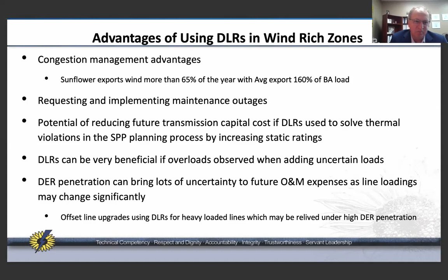So advantages of using DLR, I put them down here. Congestion management, as I showed you, there's about 1.2 gigawatt of wind trying to connect to the same hub in that area. If I continue maintaining my rating as static rating, there will be congestion. There will be times where I have to build more new lines. As a cooperative load serving entity, we like to save money, and these technologies can save us money. Maintenance outages also are getting complicated. With DLR, we could use that to our advantage. We could potentially reduce future capital transmission, as I mentioned. DLR can be very beneficial as overload absorption when adding uncertain loads. Sometimes you have oil and gas load that come in that are uncertain. You want to connect them, you find an overload. If I could use DLR to help me connect these loads until I see the exact megawatt, then I could go build transmission. That could be a time saving. And also DER penetration can change flow on the lines, and using DLR can help us manage that. Next slide.